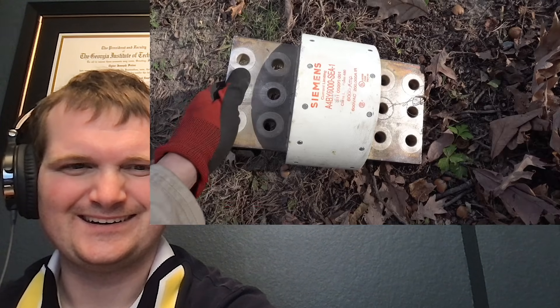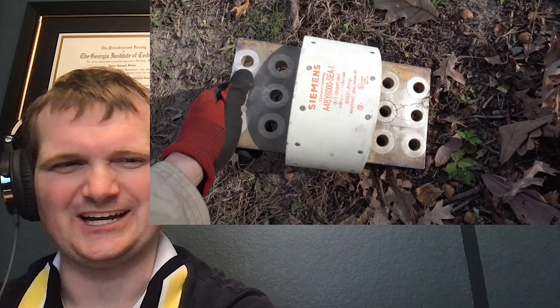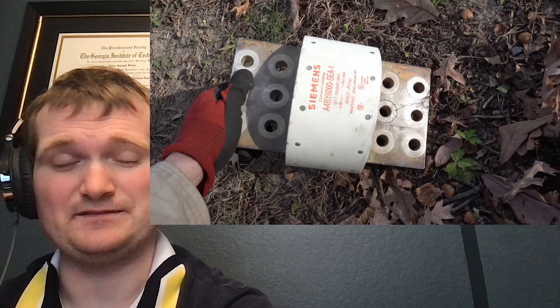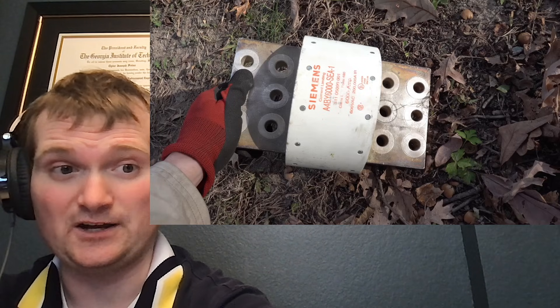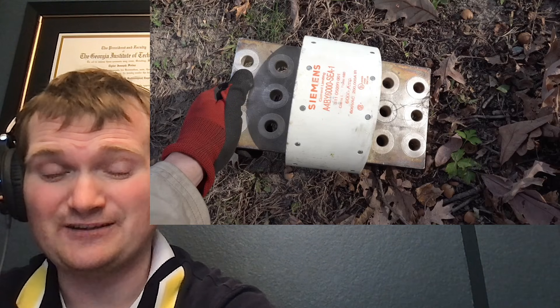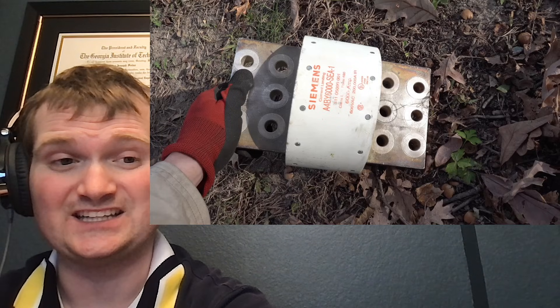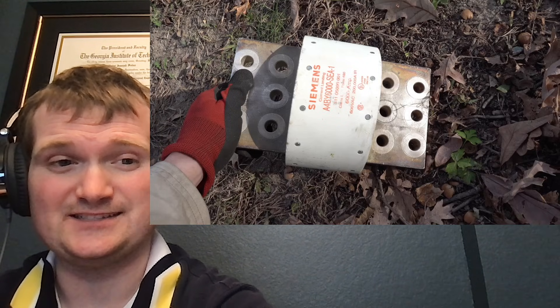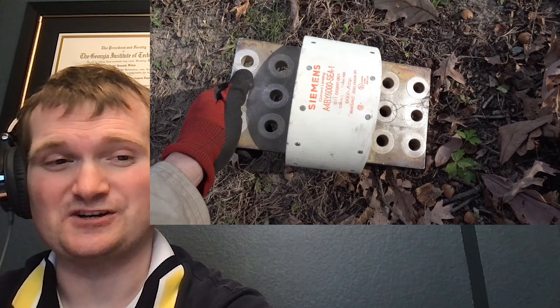The slow-mo on this one turned out awesome, even though the clamps barely held up. Most of the indium was ejected as it liquefied, mainly via magnetic forces at first, and then when the fuse finally popped it made an impressive explosion. 130,000 amps will absolutely blow apart transformer windings and create pressure waves. So there's arc flash — essentially the fire hazard, the burning bits — and then there's arc blast, the actual shock wave. Both are trained on, because if they're large enough they're both significant when dealing with significant amounts of energy.